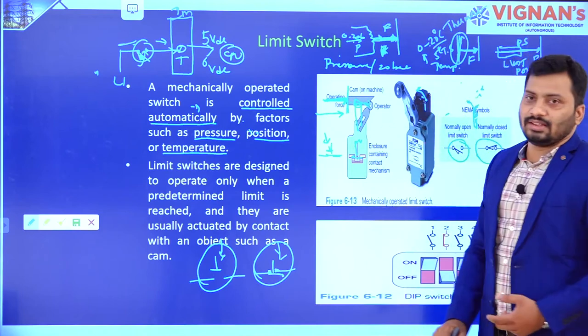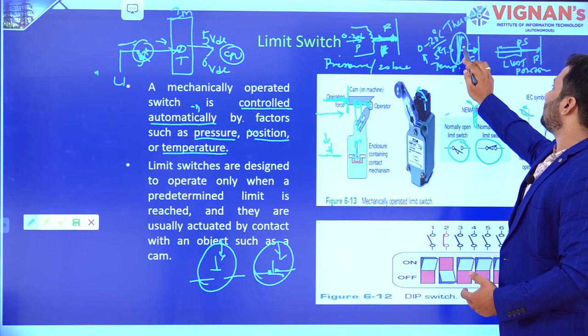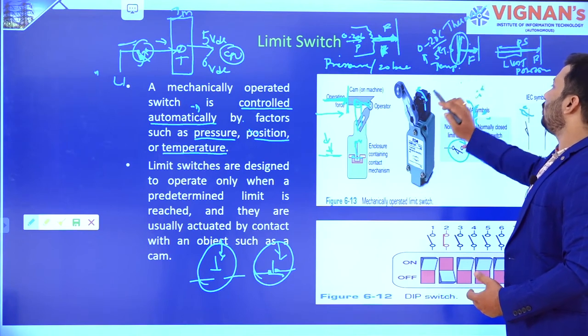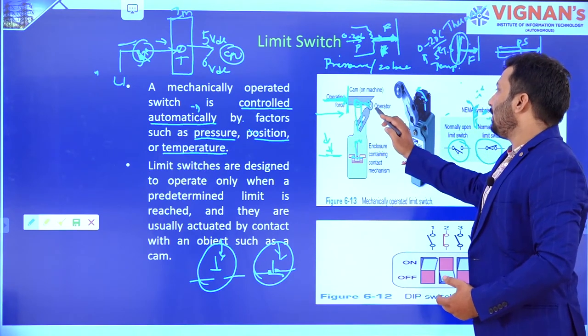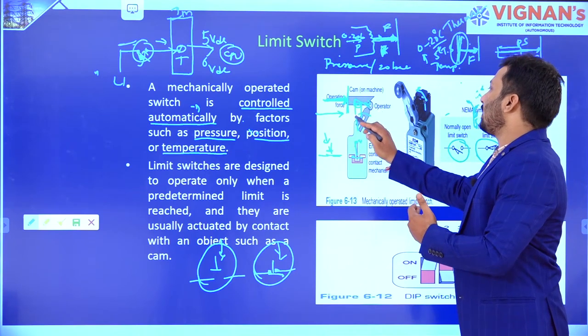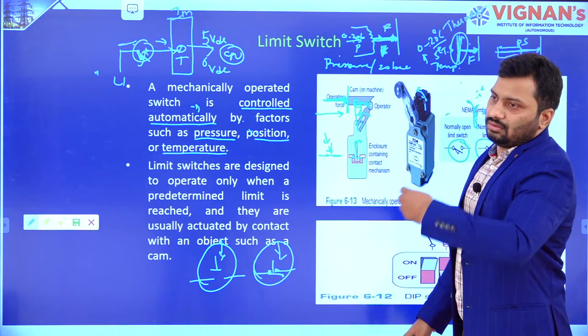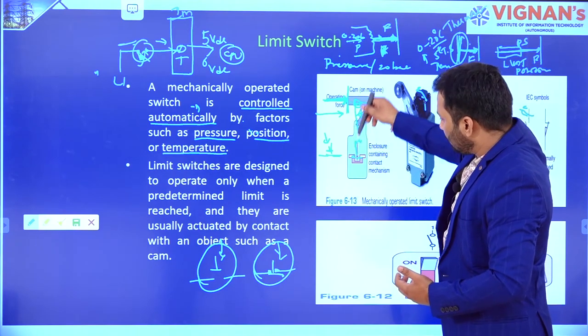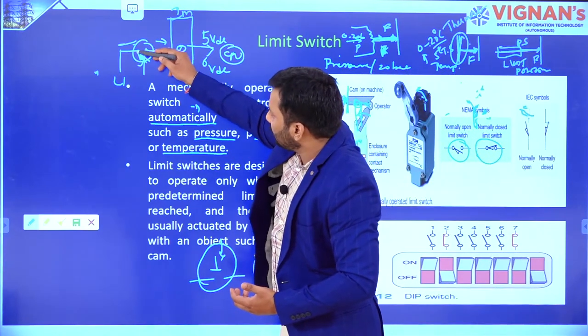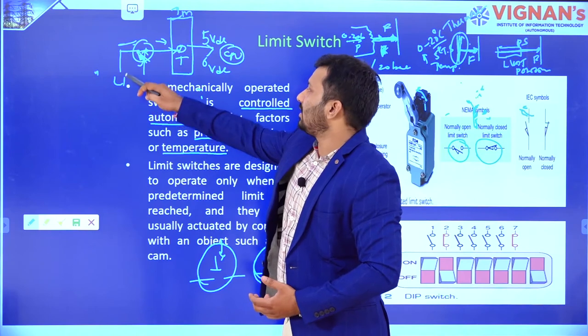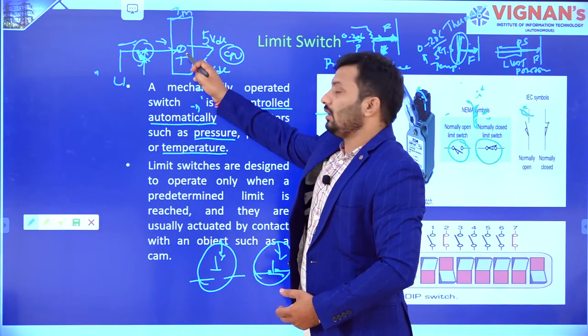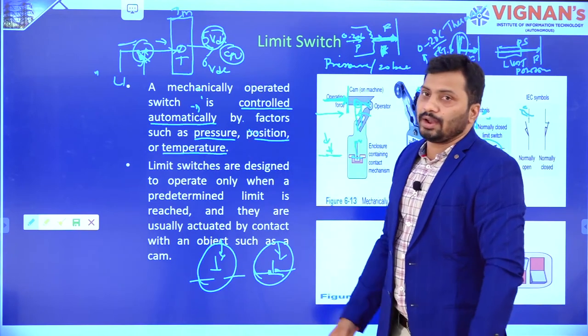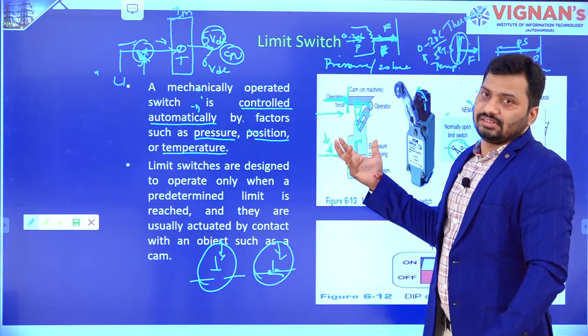Once it crosses 20 degrees, what will happen? Corresponding bending occurs in the bimetallic strip present in the thermostat, and corresponding force is going to act on this particular terminal. It is the one which crosses that particular limit — that is the reason this mechanical element loses this position and moves to the final position. Whenever it moves to this position, it gives force on this particular limit switch and it is going to be closed. Once it is closed, this line voltage acts as input to this particular terminal, internal circuitry conditions that signal, and the output you are going to get is 5 volts DC. The CPU understands that the temperature has reached 20 degrees Celsius.